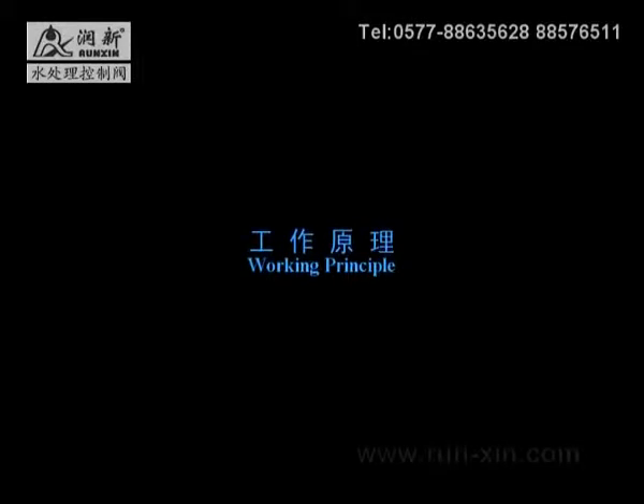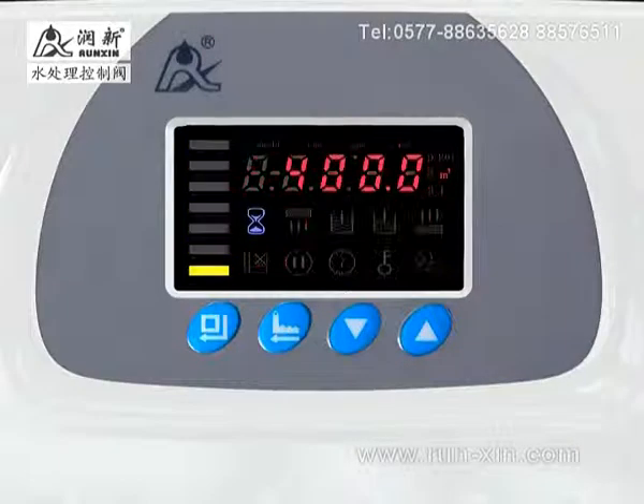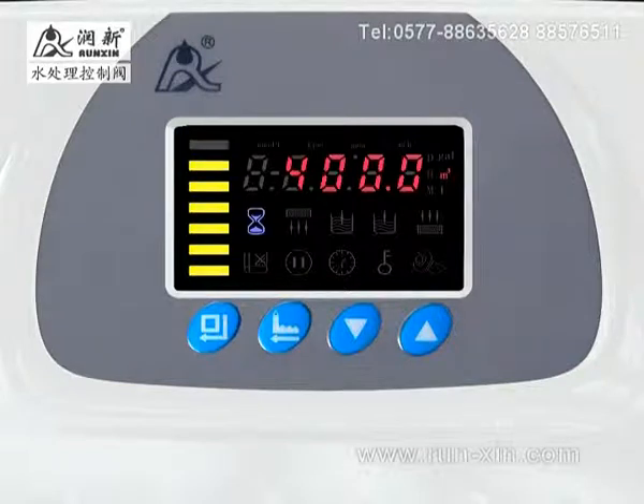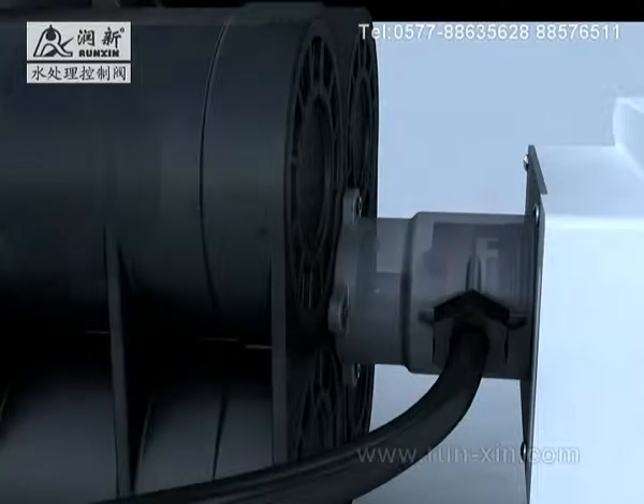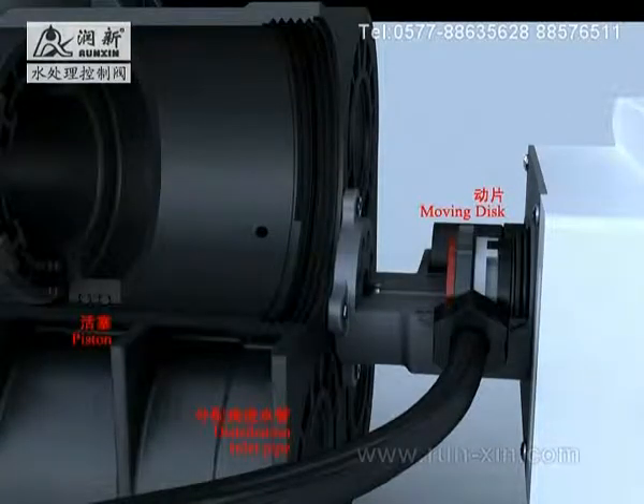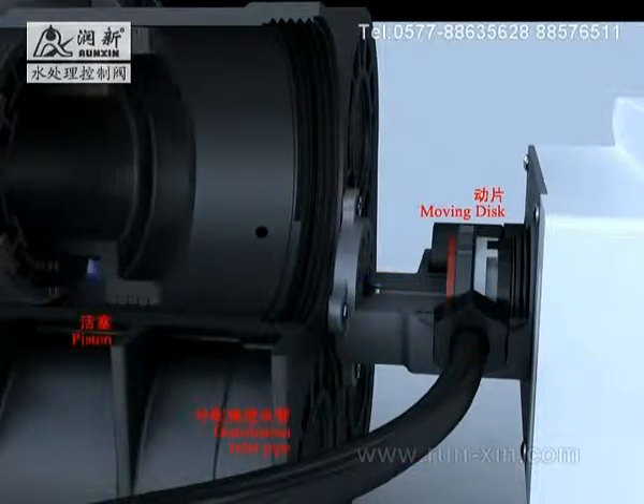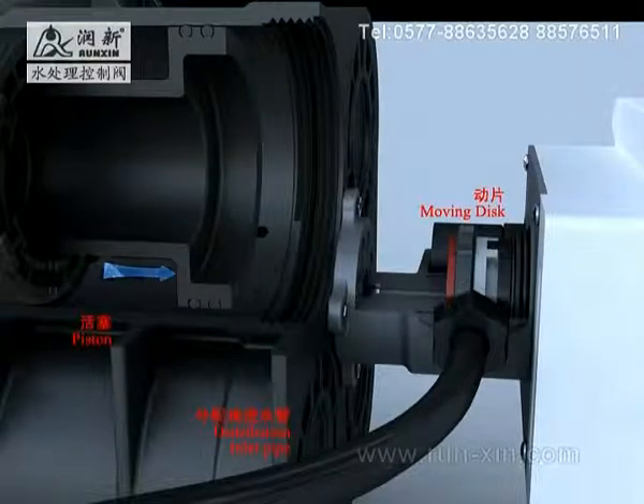System working principle. When the system is in service state, the symbol of service state lights. The motor controlled by the main control board drives the big gear to rotate, and also drives the moving disc, which is fixed with the shaft. When the relative angles of the moving disc and fixed disc change, the flow channels are changed. Small parts of raw water go into the distribution valve through 4 chambers and control pistons opening and closing to change its flow channels.